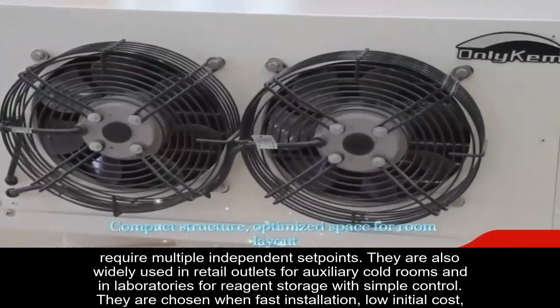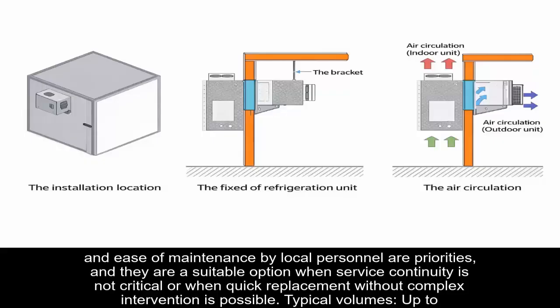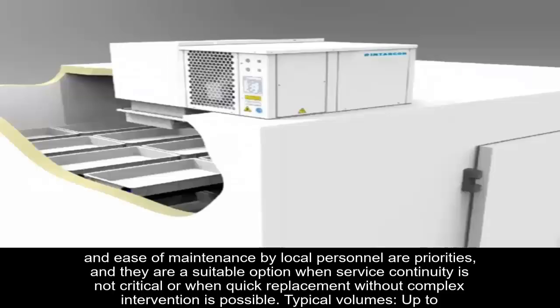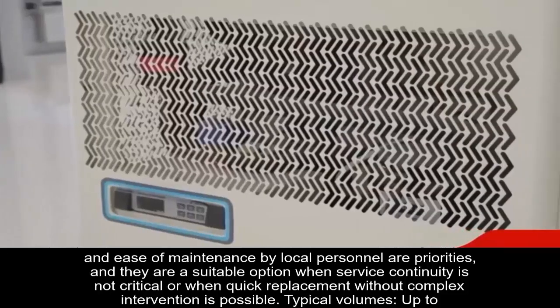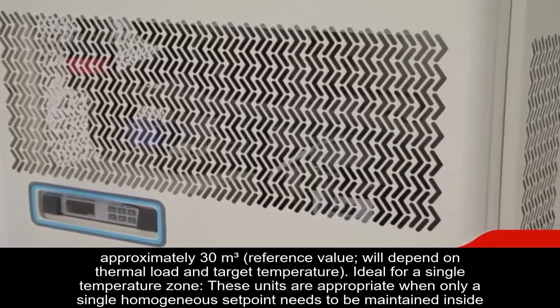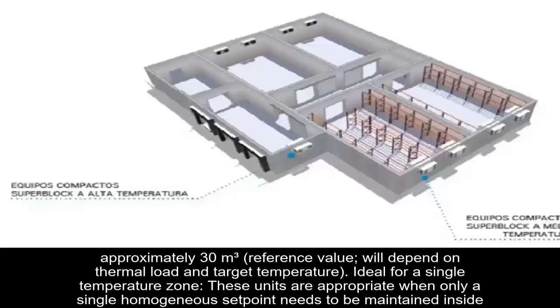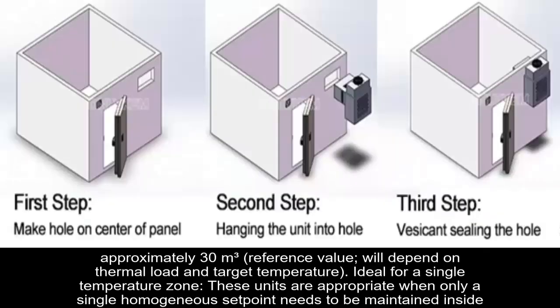They're chosen when fast installation, low initial cost, and ease of maintenance by local personnel are priorities, and they're a suitable option when service continuity is not critical or when quick replacement without complex intervention is possible. Typical volumes: up to approximately 30 cubic meters, reference value, will depend on thermal load and target temperature. Ideal for a single temperature zone.